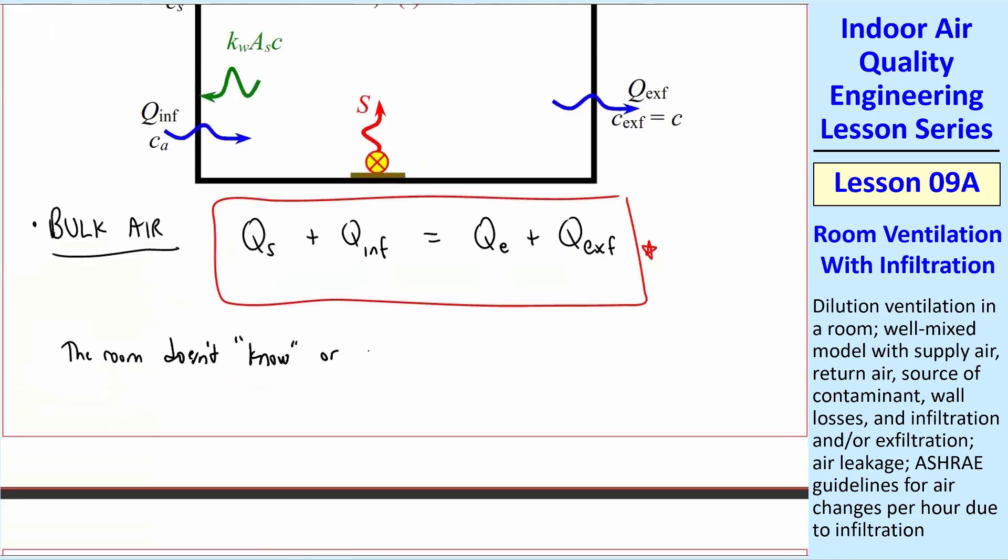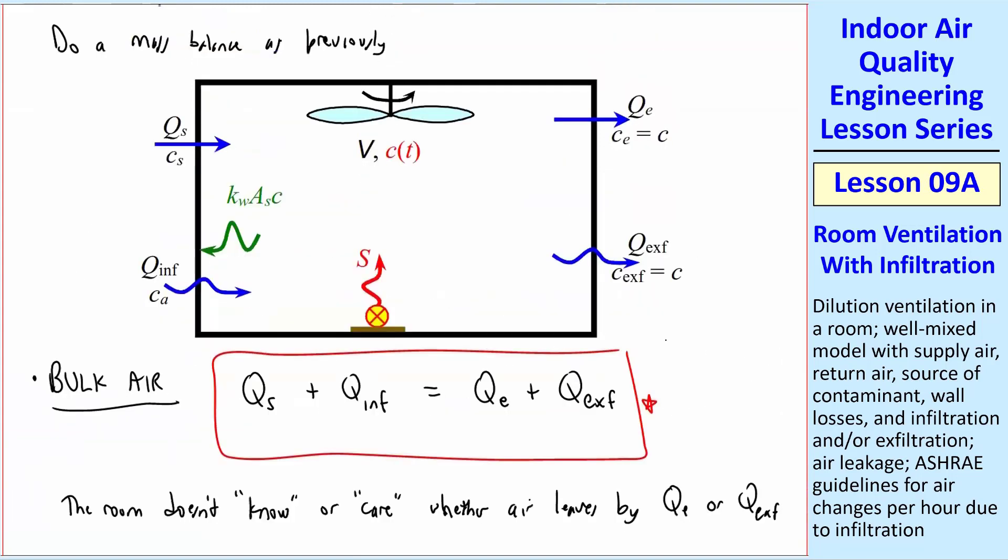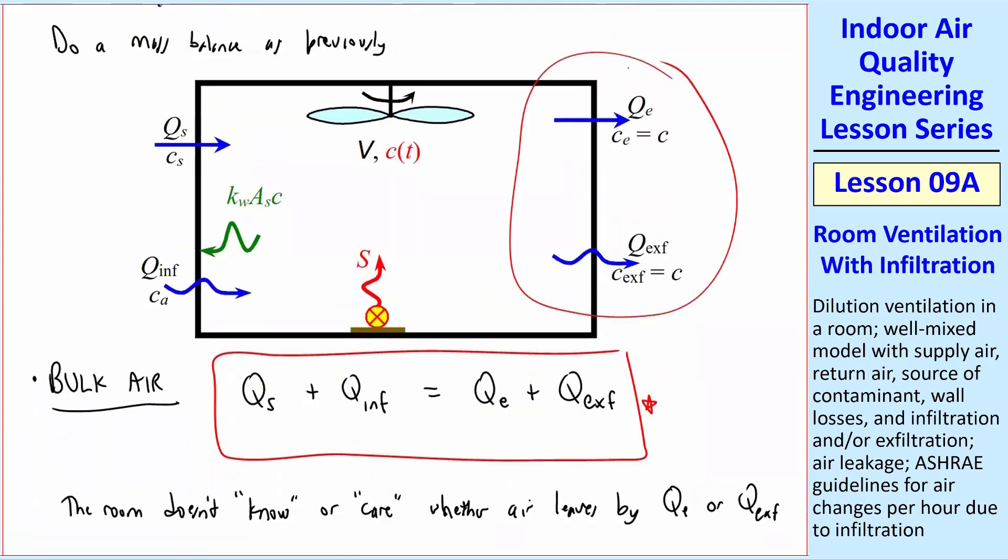The room doesn't know or care whether the air leaves by Q_E or Q exfiltration. What I mean by that is this. If you look at these two outflows, they're both at the C inside the room. So if you think about it, from a mathematical point of view, as we're analyzing this room, suppose the room is at very low pressure compared to the outside. So there's no exfiltration. So all the air has to come out through the normal exhaust. Or suppose your exhaust is blocked somehow, and whatever you're forcing in here plus whatever comes in through infiltration is going to all have to come out through exfiltration. But typically it's a combination of these two.